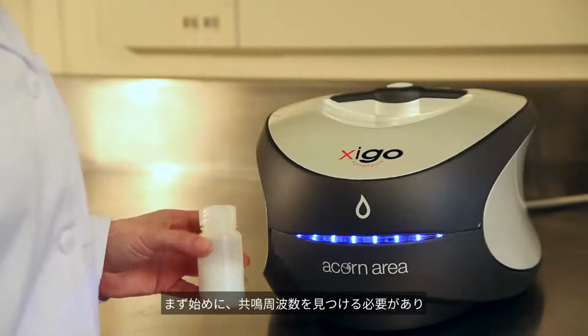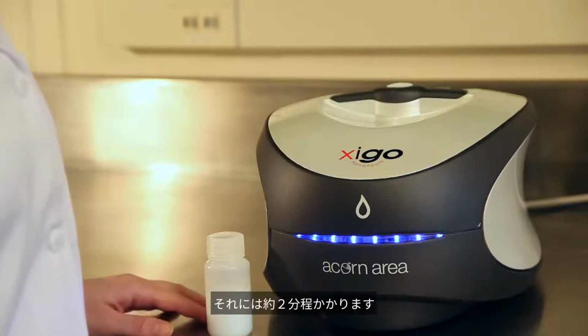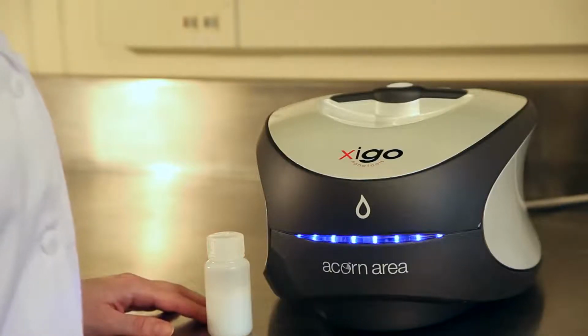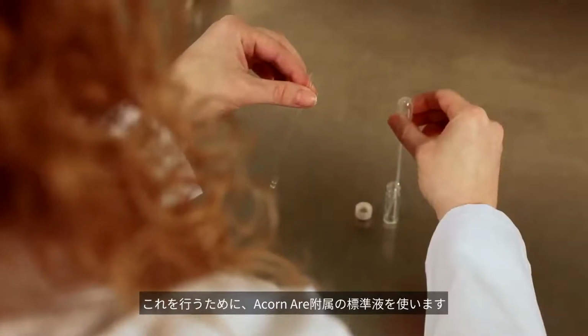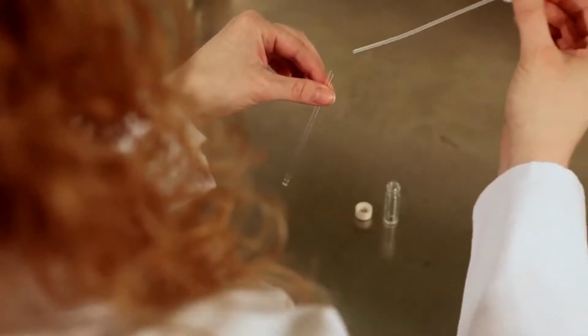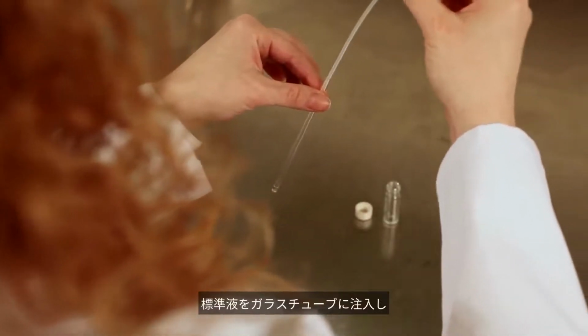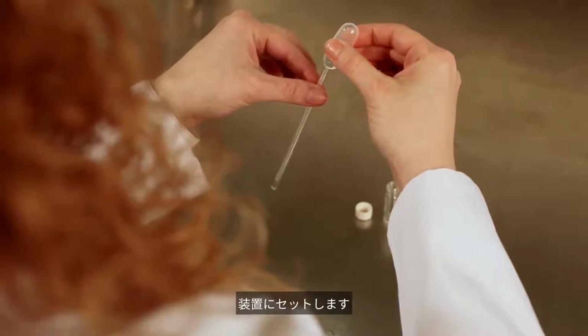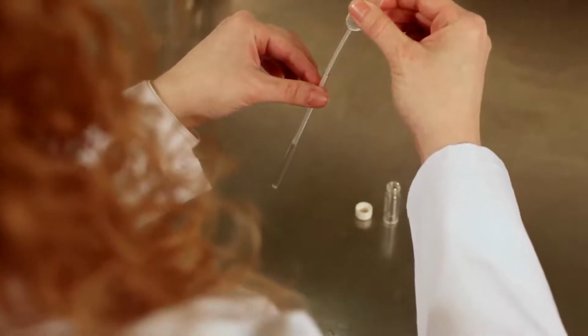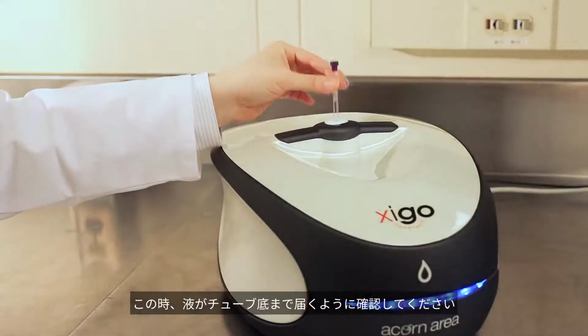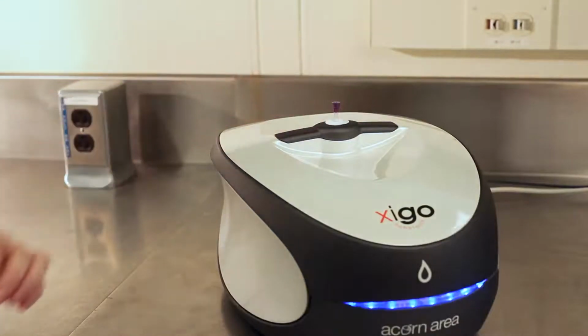I'll be using a 30% weight suspension of silica nanoparticles. But before we make a measurement of that sample, we need to find the resonant frequency, which will take about 2 minutes. To do this, we use a verification standard that is provided with the Acorn Area. To make a measurement, simply fill the NMR tube with the standard and then insert it into the instrument, making sure it reaches the bottom.